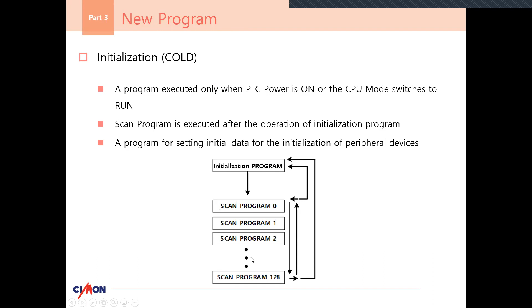Then on the opposite side, we have initialization hot. This would be used for a momentary blackout. The only caveat is you have to be able to predict how long the blackout is. If it's something you're controlling, that will be easy to predict. So if you want to shut the power off for 2 minutes, you would write that program in your PLC telling it in case of a momentary blackout happening for 3 minutes, store this data on the side, and shoot it back into the scan program after that.